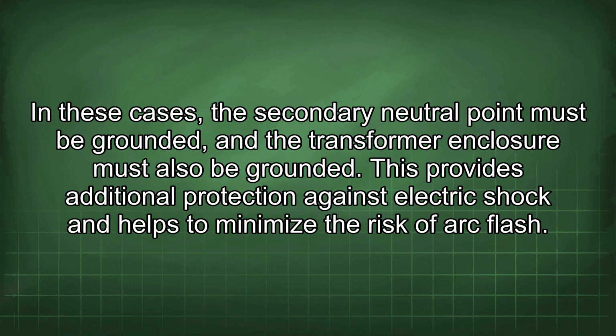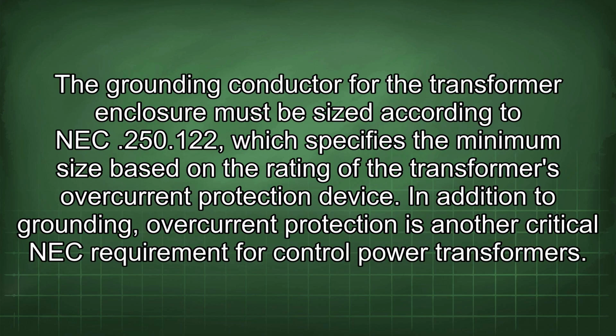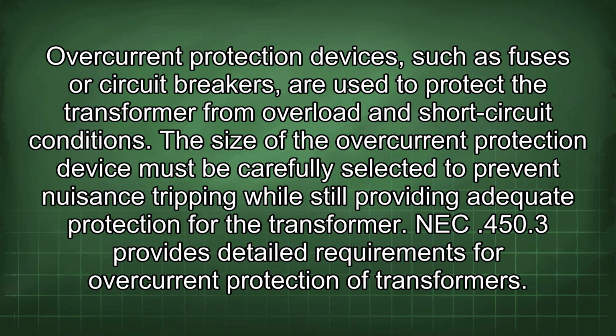This provides additional protection against electric shock and helps to minimize the risk of arc flash. The grounding conductor for the transformer enclosure must be sized according to NEC 250.122, which specifies the minimum size based on the rating of the transformer's overcurrent protection device. In addition to grounding, overcurrent protection is another critical NEC requirement for control power transformers. Overcurrent protection devices, such as fuses or circuit breakers, are used to protect the transformer from overload and short-circuit conditions. The size of the overcurrent protection device must be carefully selected to prevent nuisance tripping while still providing adequate protection for the transformer.